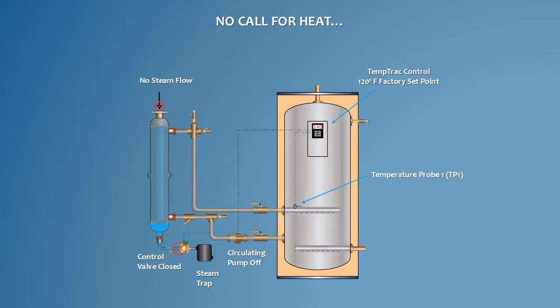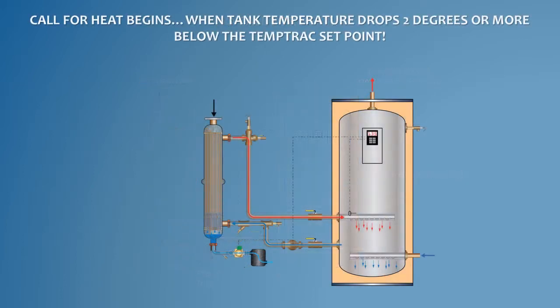The Cobrex water heater operates to satisfy the temperature set point of the TempTrac digital operating thermostat located in the front control panel. The TempTrac operating sensor, Temperature Probe 1, is located in the storage tank just above the circulating pump piping connections. The TempTrac is factory adjusted to a set point of 120 degrees. This set point can be adjusted to the desired stored water temperature required to maintain your specific system design requirements. When there is no hot water demand, the condensate control valve is closed to shut off steam flow through the heat exchanger, and the pump is de-energized to stop the circulation of heated water from the heat exchanger to the storage tank. When there is a demand, hot water exits from the top of the storage tank and is replaced by cold water entering into the bottom of the storage tank.